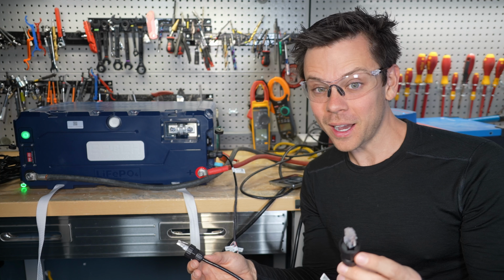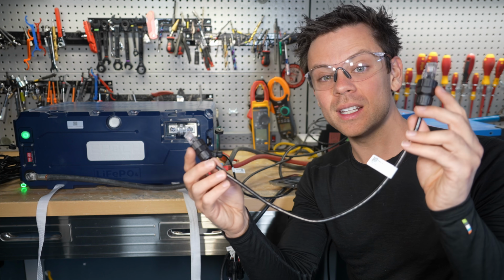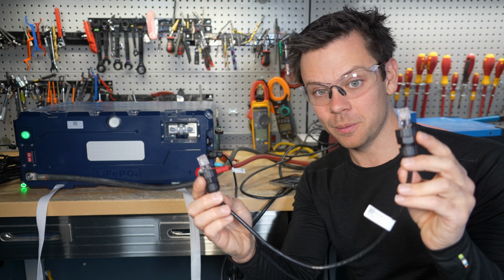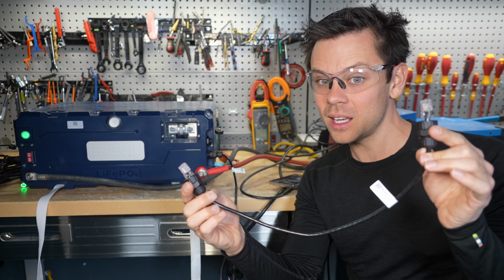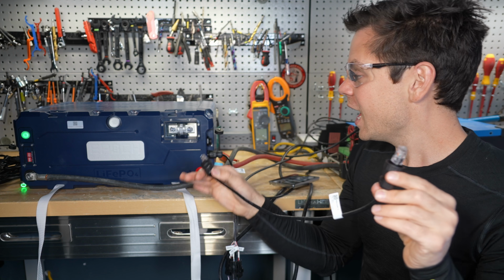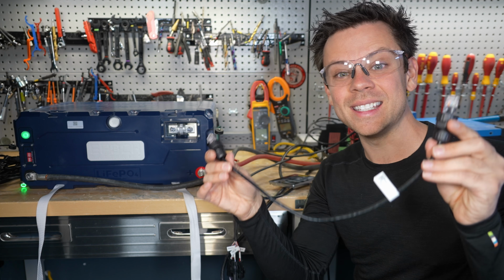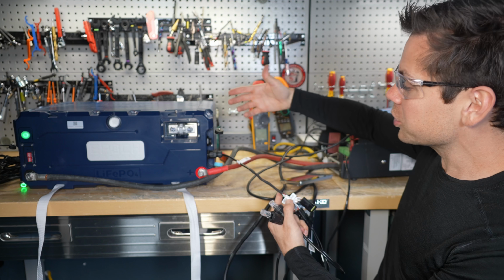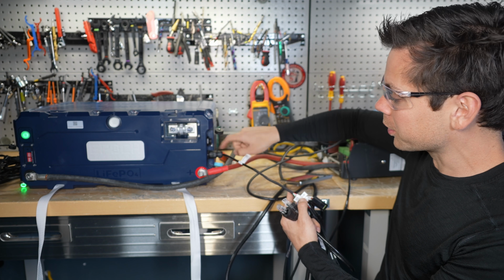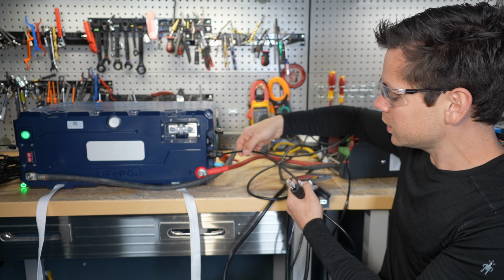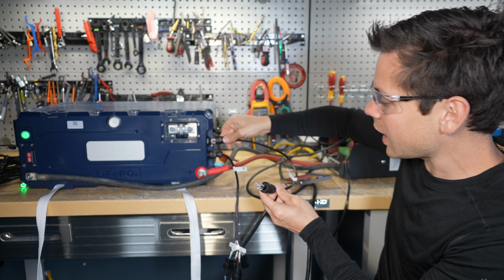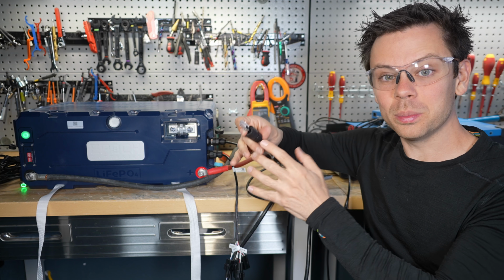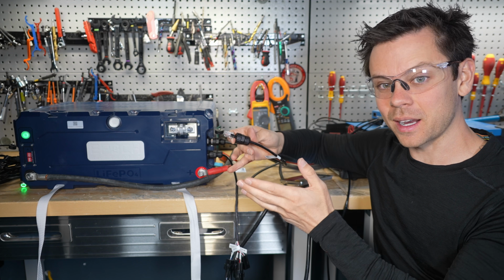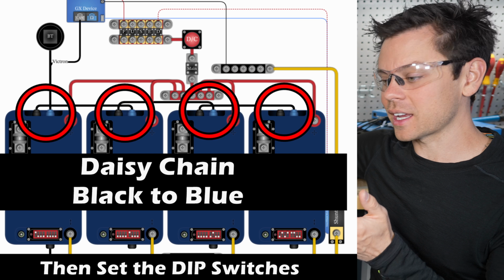Now, if you have multiple batteries connected in parallel, you want to connect them together with this small black cable. This will allow the batteries to communicate with each other in the Victron system, and you need to connect them in a daisy chain configuration. So if this is battery number 1 and the blue port is connected to your Victron system, this cable will plug into the black port, and the other side will plug into the blue port on the second battery. Here's a diagram to show that connection.